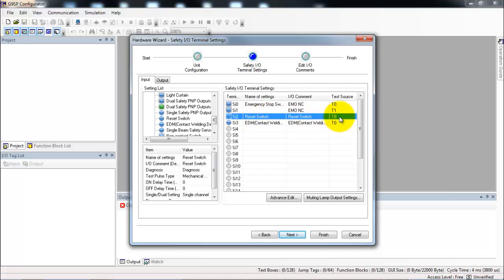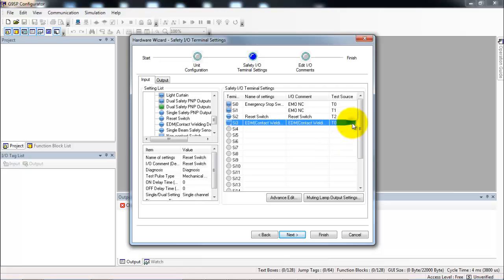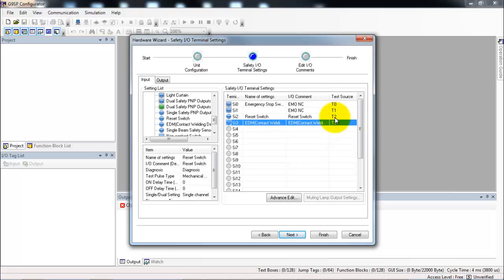The next thing I need to configure is my test source. While it would be okay to use test output 0 for the reset and EDM, I physically wired them to test output 2 and 3. If you have additional, it's always good to spread them around. It can only help with your troubleshooting.